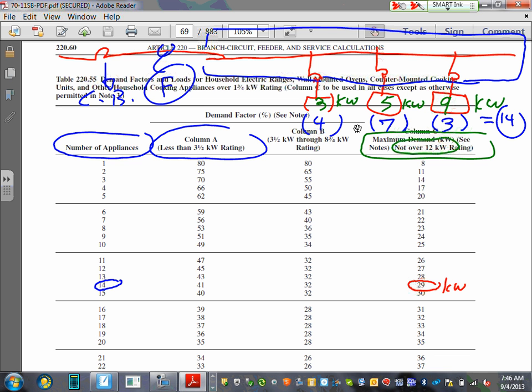From the get-go, all of them less than 12, you apply that rule. Any question about that? They're all less than 12. Add them up. How many of them do I have? 14. And go all the way to 29 kW. So for all practical reasons, I can use 29 right now. By the way, if you multiply 4 by 3 plus 7 times 5 plus 3 times 9, you're going to hit a big number. Now you chopped it down to 29 because of human behavior.